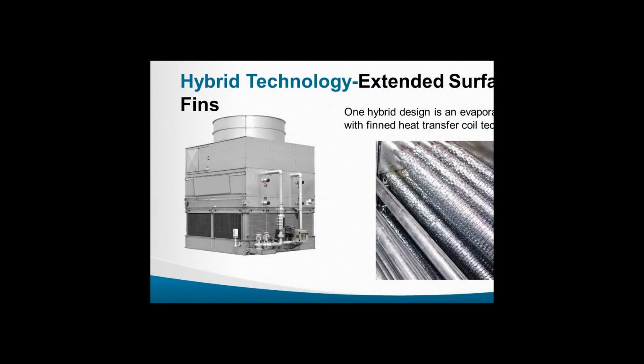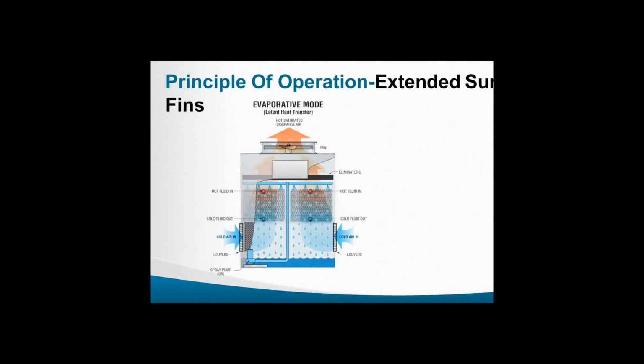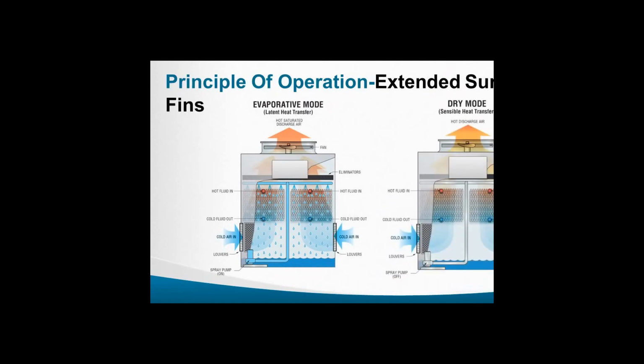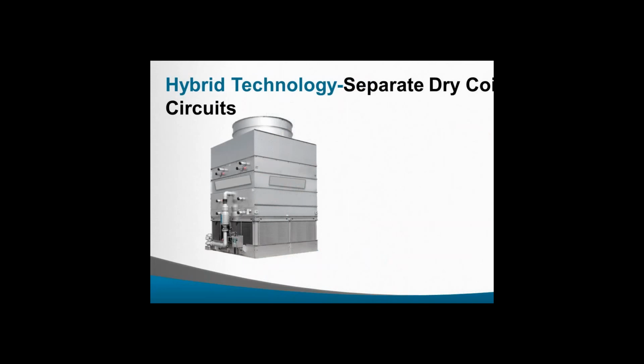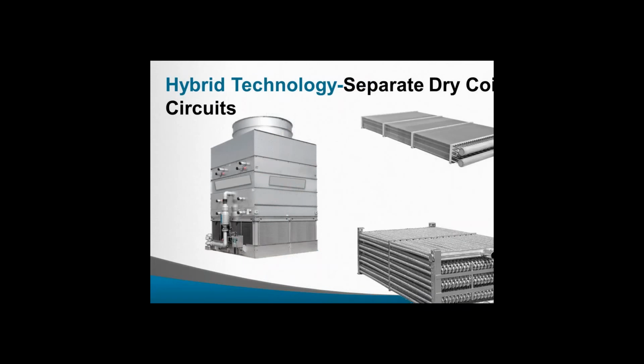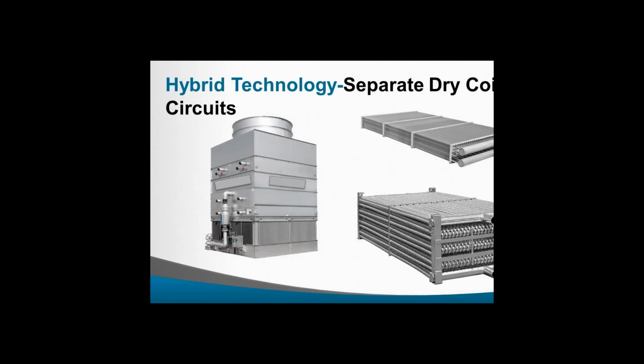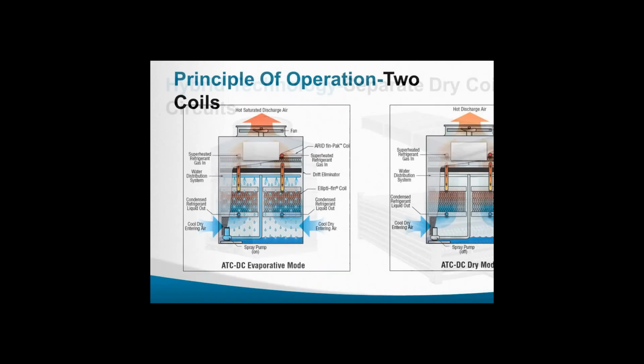So looking at the first technology, this is just a bare tube coil that's finned. You can run that wet or dry. So operationally, on the left, this is evaporative mode. And then with that finned coil, you just run the fan, you run it dry, you save water. But it's either wet or dry. So you also have a combination where you put a dry coil in series with that wet coil. You'd run the water through the top section, which gives you some plume abatement.